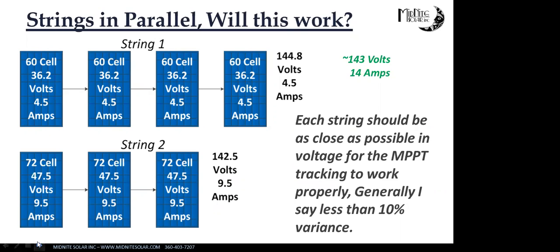And the thing to remember here is that your strings, each string has to be within a certain voltage of each other, but each module in that string has to be within a certain current of each other. So as you see here in example 1, string 1, you have 36.2 volts and 4.5 amps, but all 4 modules are uniform. So you have 144.8 at 4.5 amps. But then in string 2, you only have 3 modules, but it still comes out to 142.5 and 9.5 amps.